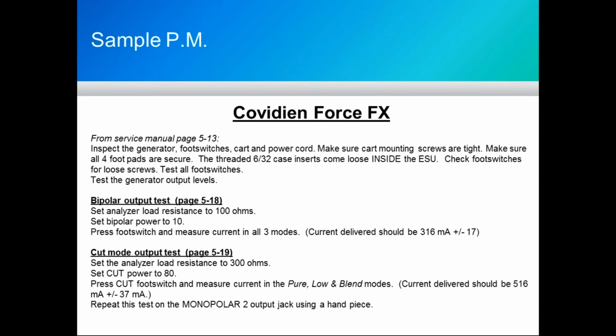So for bipolar, you start out with 100 ohms, and you set the bipolar power to 10. In Covidiens, they were looking for the mA output. So when you go through all three modes, you want to make sure that the mA output is 316 plus or minus 17. Then for cut, you change the resistance you're testing with to 300 ohms, set the cut to 80, and run through all the modes. The mA should be 516 plus or minus 37.